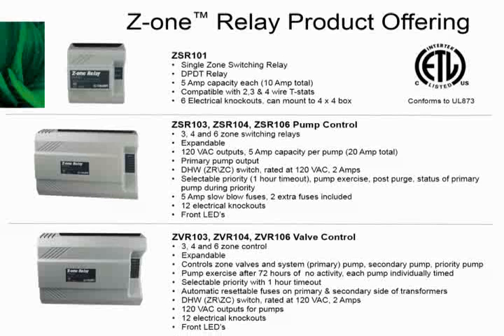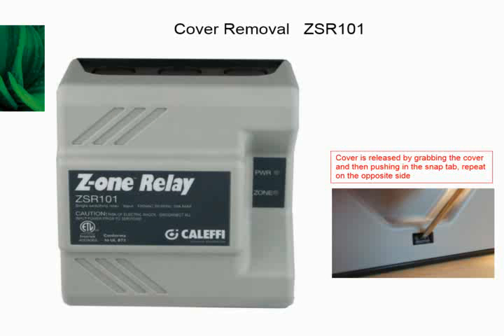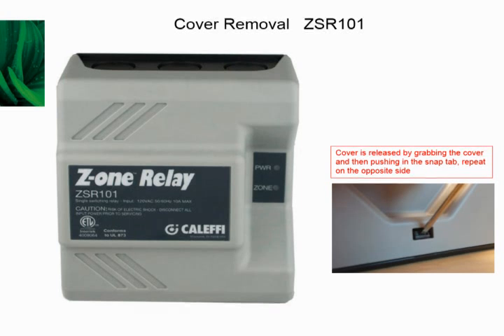So let's keep rolling here. We'll focus in on the single zone. We use a snap fit cover on these. It does require a tool to open up the cover. You're going to need a screwdriver. The best way to open it is grab the cover and just give that snap arm a tap, and then spin it around, do the opposite side, and the cover will lift straight off. But if you're on the small unit, you do have to release both snap arms before that cover is going to come off for you.